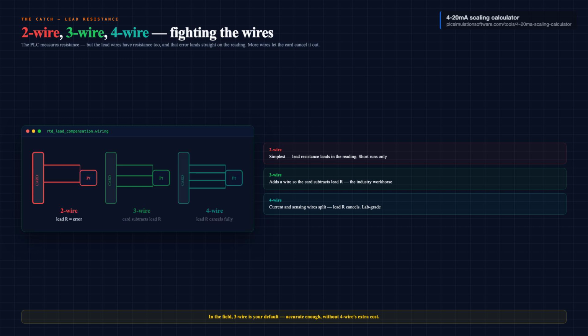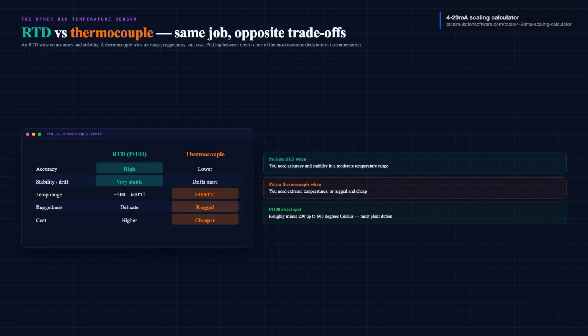So how does an RTD compare to the other big temperature sensor, the thermocouple? They solve the same job in opposite ways. An RTD is more accurate, more stable, and easier to read, but is limited to roughly minus 200 up to 600 degrees Celsius, costs more, and responds a little slower. A thermocouple is the opposite. It covers a huge range, well over 1,000 degrees. It is rugged, fast, and cheap, but it is less accurate and it drifts more over time.